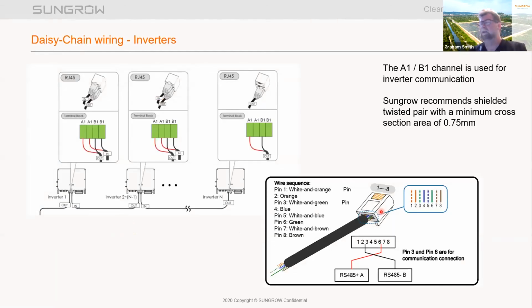Connection wiring. Now, RS485, if you haven't used it before, it's basically a 2-wire system. It's data positive and data negative. That's it. It may have a shield around it, or it may not, but our system just uses the positive and negative. On the inverters, there are 2 channels. There's an A1B1 and an A2B2 channel. Now, I'll go into that in a bit more detail in a moment, but the inverters always connect on the A1B1 channel. A1 is positive, B1 is negative, and basically the daisy chain.